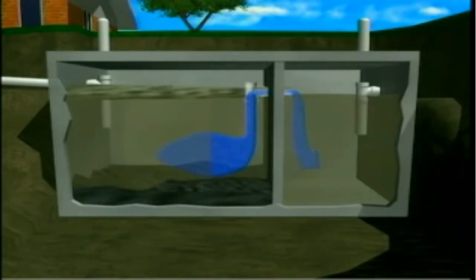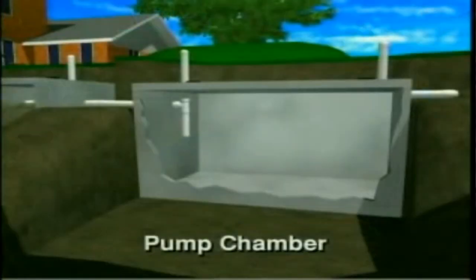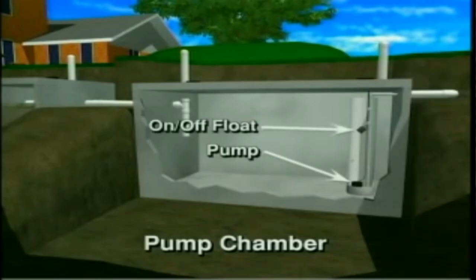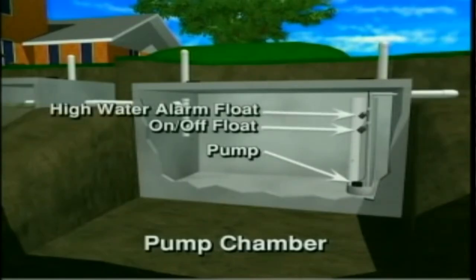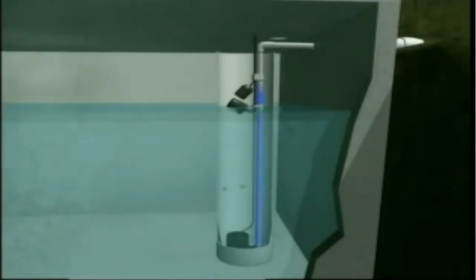The dosing chamber, or pump chamber, collects the effluent that flows from the septic tank. It's constructed of concrete, polyethylene, or fiberglass, and is fitted with a pump, a pump control float, and a high water alarm float. Once the effluent in the tank reaches the level of the control float, it triggers the pump to turn on.